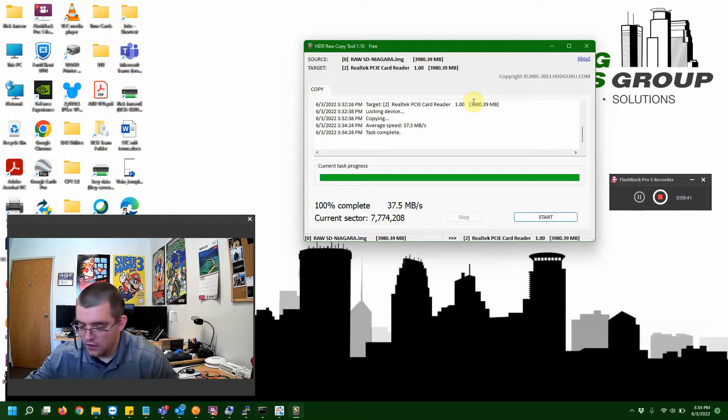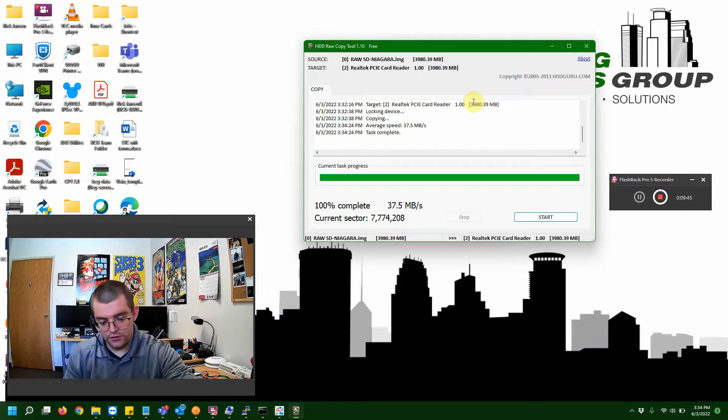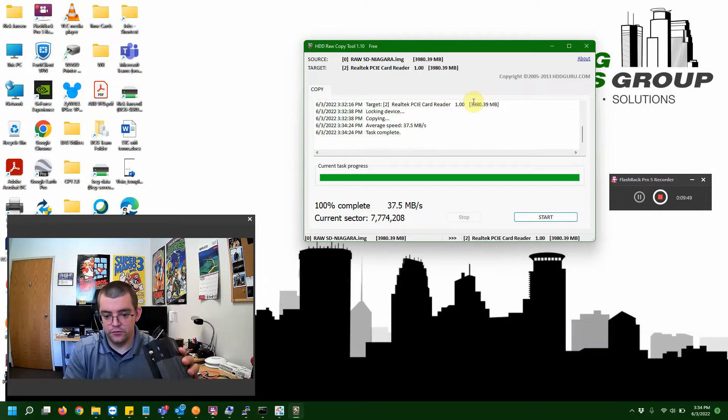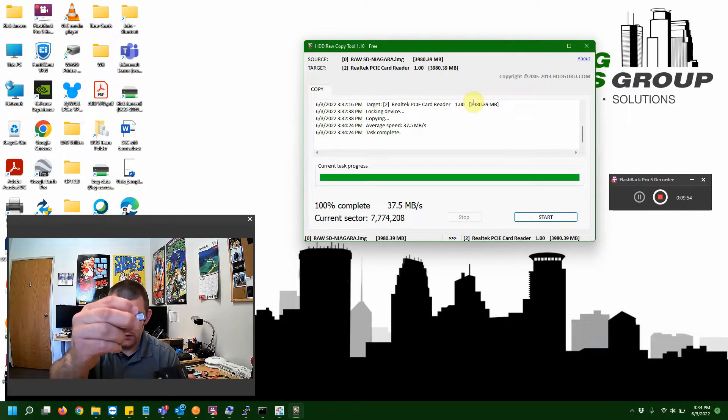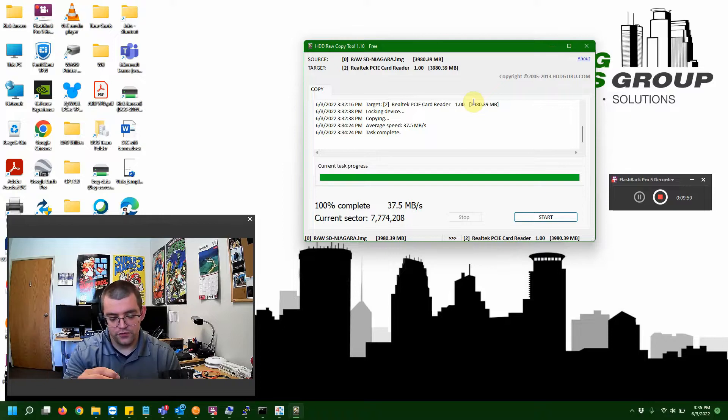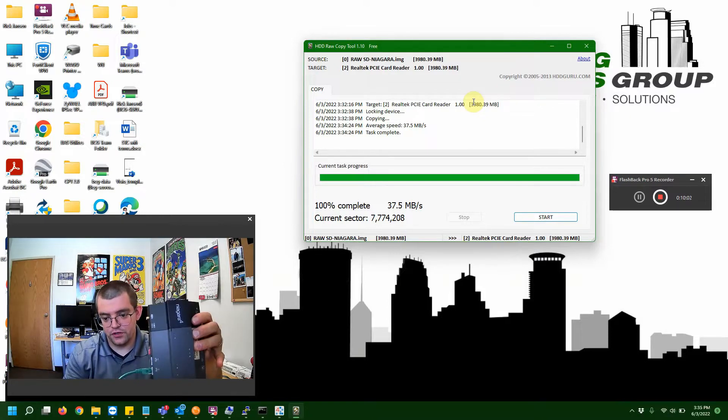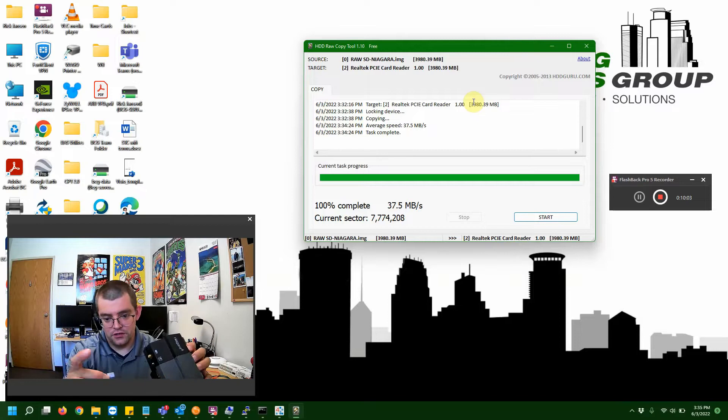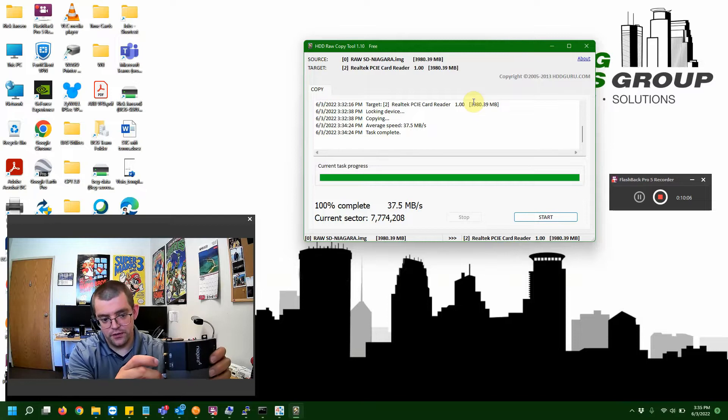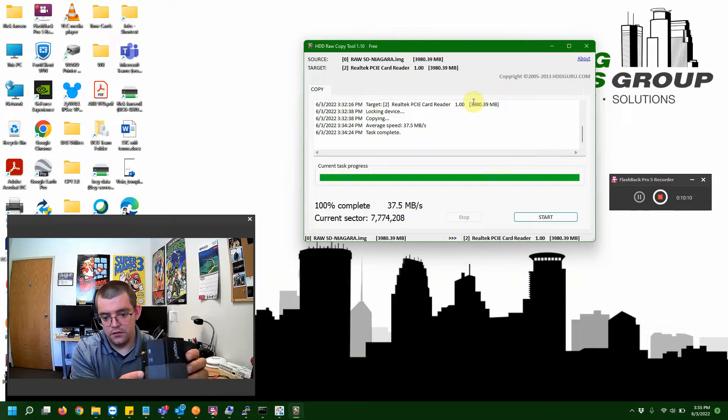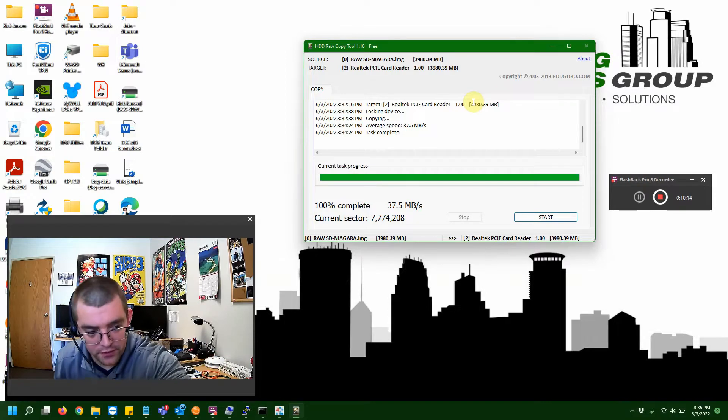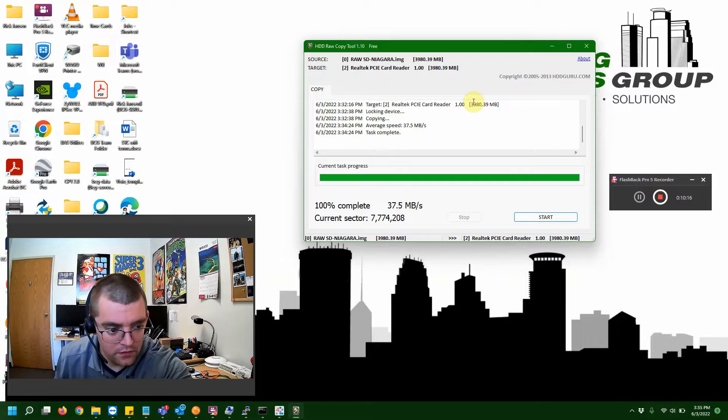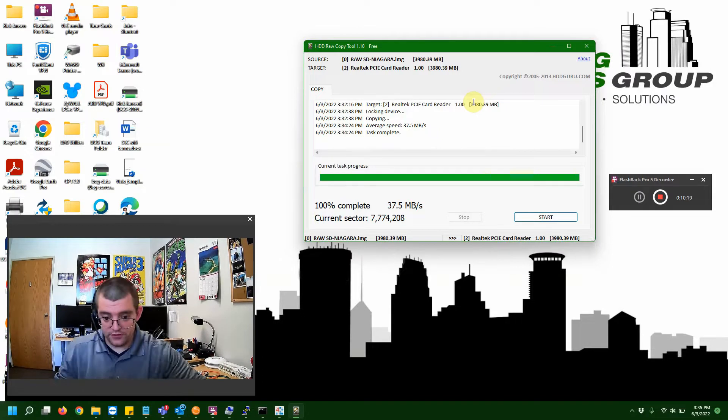I'm going to unplug it from my computer. I'm going to pop it on my SD card holder. And, we're going to go ahead and put it back into our Jace here. Again, I got that little slot. Typically, the little QNX here, or the code always points towards the front of the Jace. This being the front of your Jace like this, it's going to face forward like this. So, we're going to go ahead and plug that back in. And, there we go. Close the door, and I'm going to put it back on my test bench here.